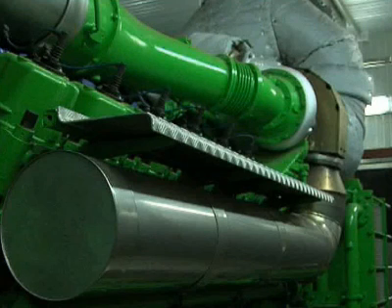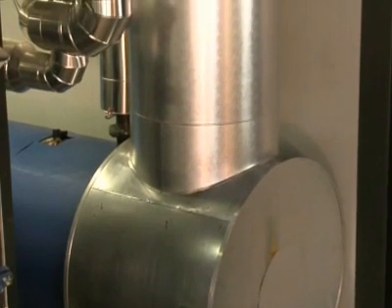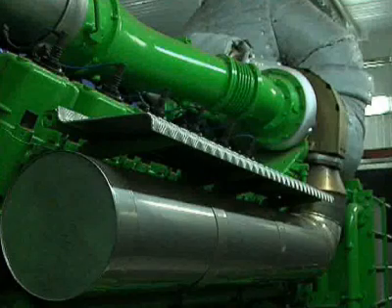It's envisaged that it will run for in excess of 5,500 hours a year and deliver a minimum of 8,875 megawatt hours of electricity. Next to the CHP enclosure is the waste heat boiler, which utilizes the exhaust gases produced from the CHP generators to heat both museums.